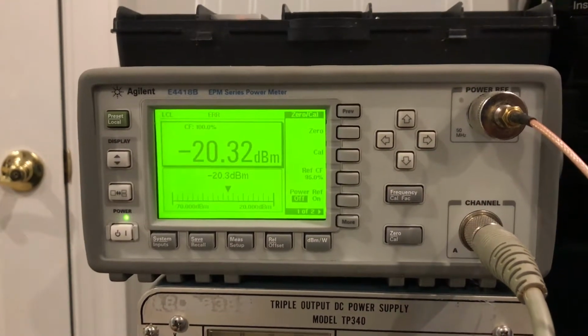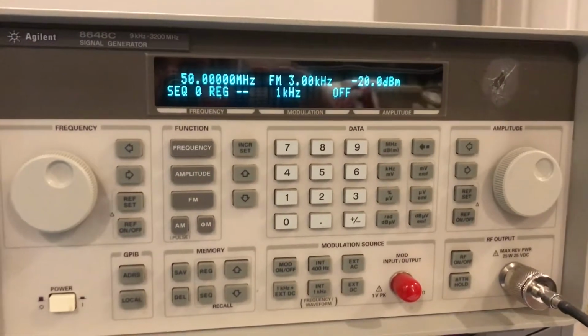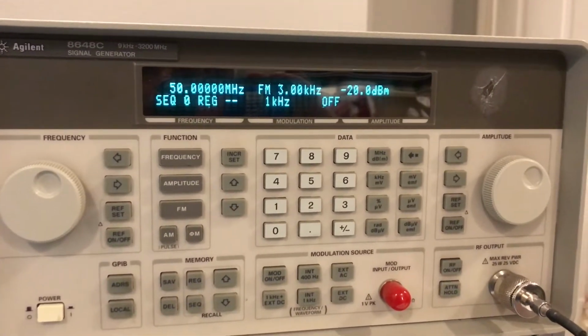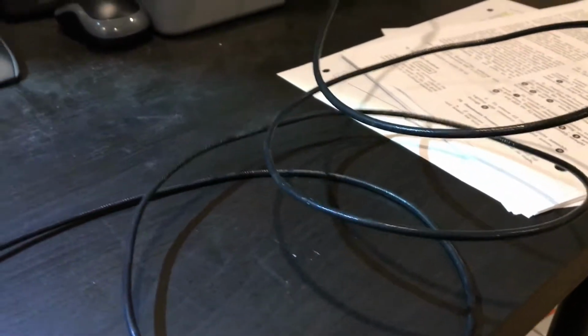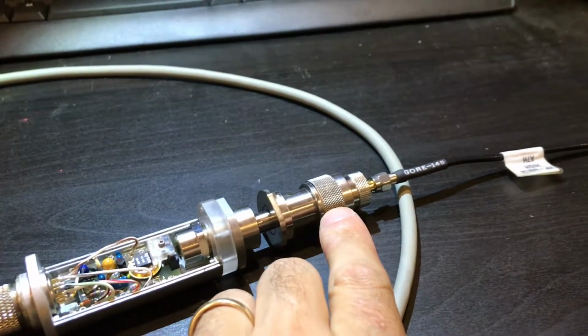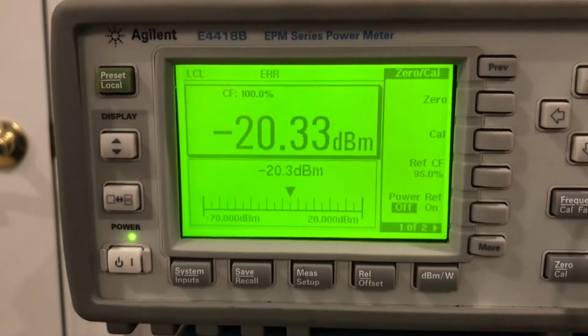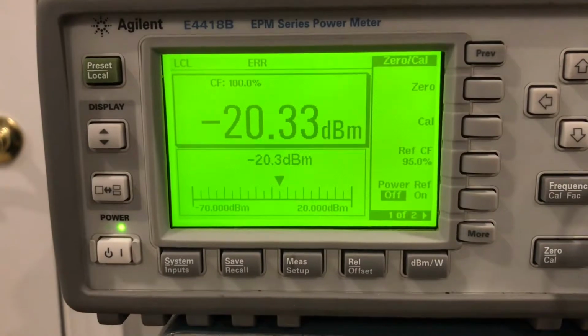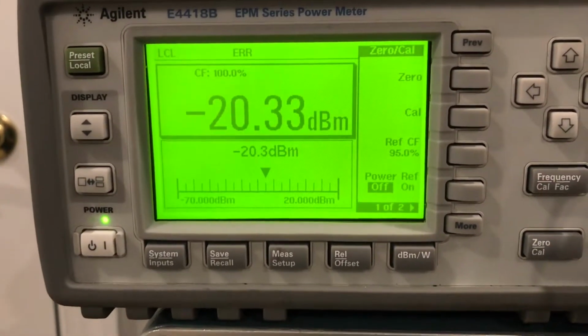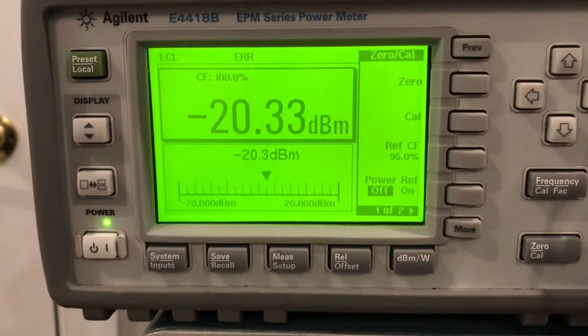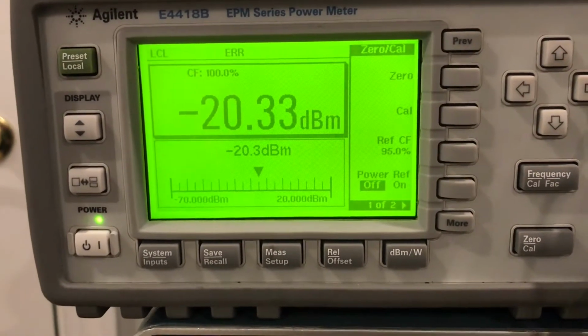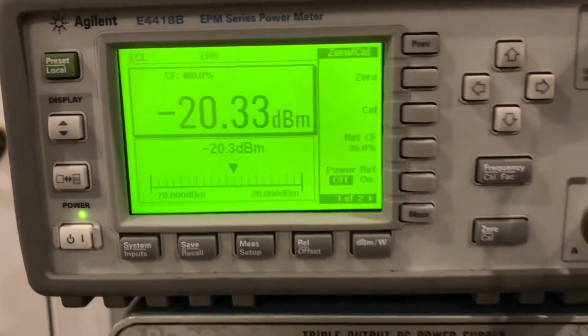But here's the funny thing. I've set up my signal generator with a 50 megahertz signal at minus 20 dBm, feeding it through this relatively long piece of coax into the sensor port, and the power meter here is showing minus 20.33 dBm, which is reasonable, since it's fair to assume at least 0.3 dB of signal loss in that cable.